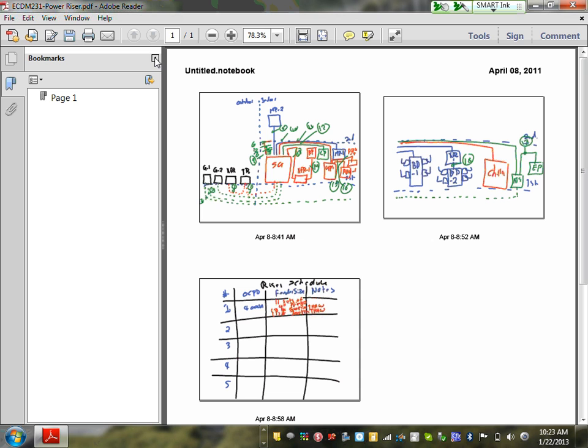And then at that point it will get confusing. You may want to contact me when you're laying out the gear. If you have a bunch of busway runs, there's only so many busways we can run out of the top of a section, and normally it's maybe two. If you start getting more busway runs, then we may get more sections, not just because of how many breakers you have, but because of how many busway connections you can make in the section. I'm going to say a maximum of two busways out of each section. I've got them to tag more than that, but it gets really complicated, and then your lead times on the gear go way off because it's special engineered. So in general, you can normally fit two up top.